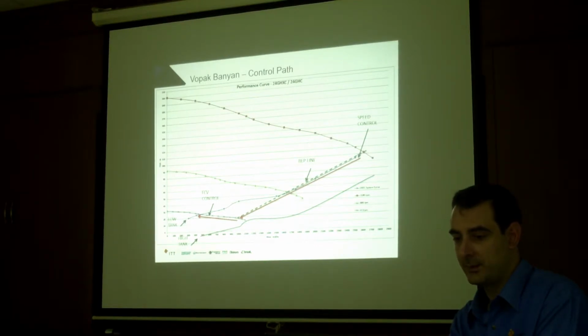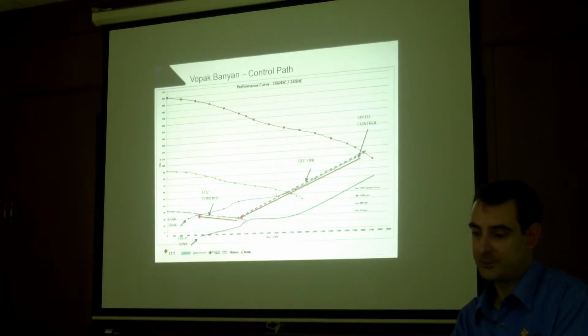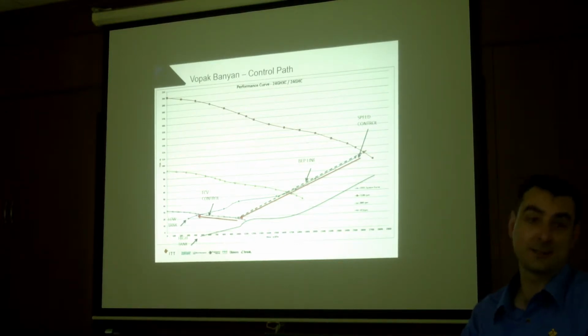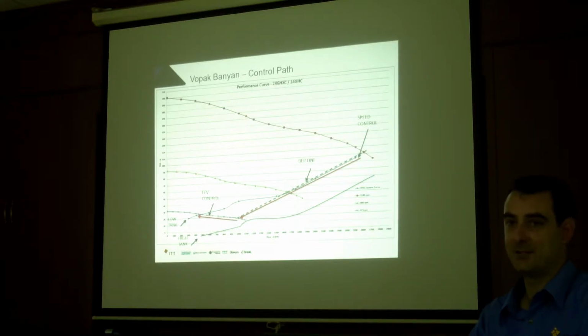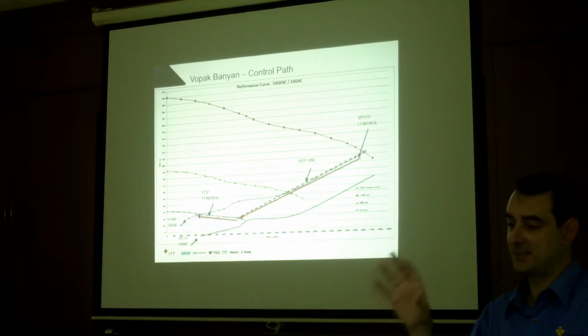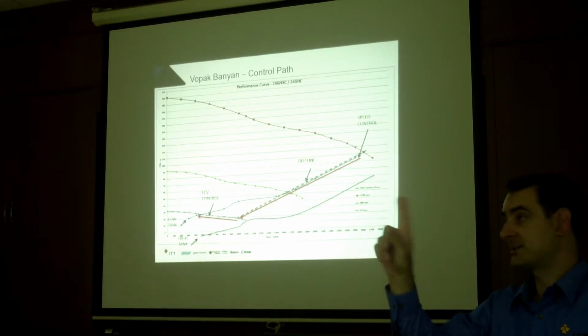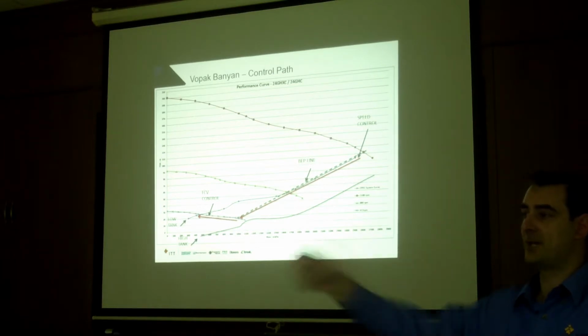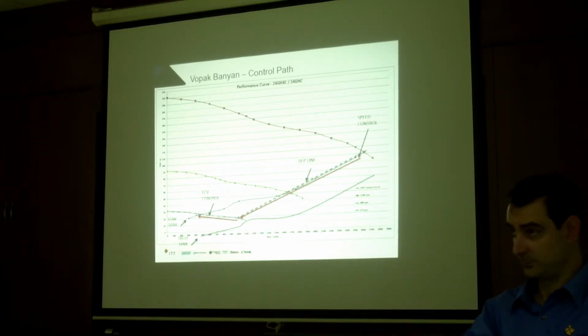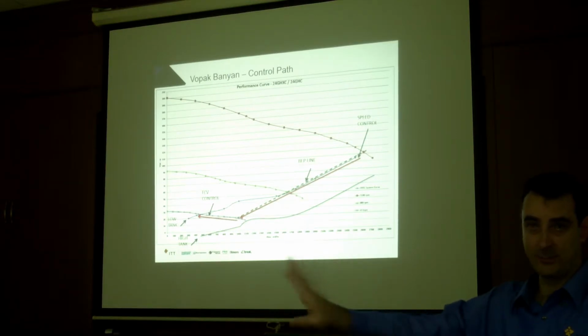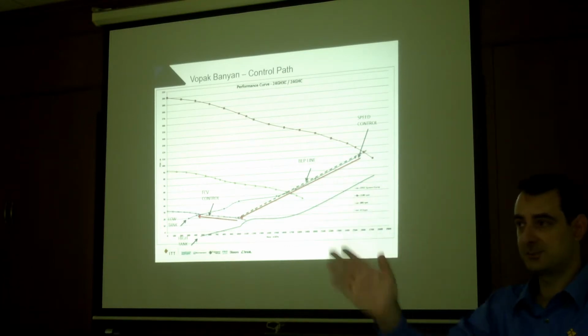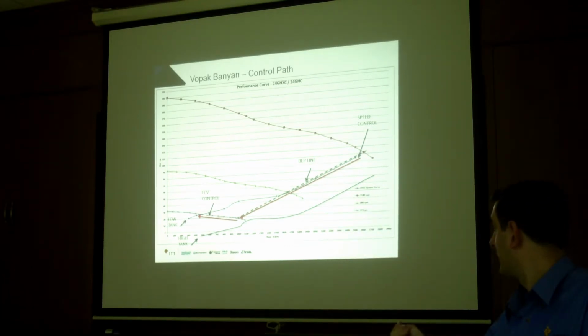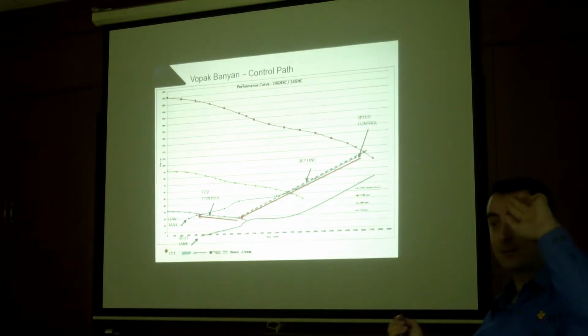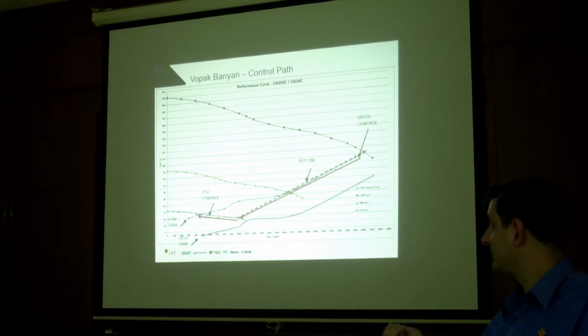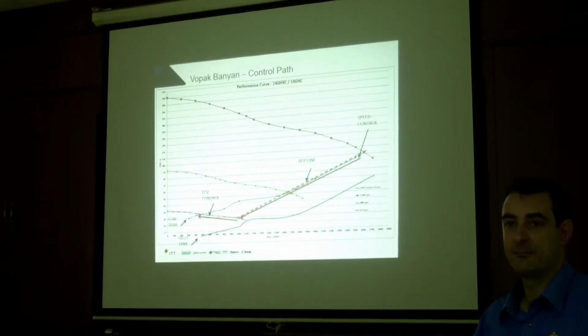Now, in terms of that, that's a medium voltage one. For the low voltage, I have a customer, again another Vopak customer, but a different site, where they had those Danfoss drives. We are using the percentage BEP value, sending it to the SCADA, to the DCS, the control room, and then they can see where they are, and if they're past 110%, they will send someone out to the field to shut the valve a bit. Once they shut the valve once, they will never need to worry about it again. The variable speed drive will do the rest, increase speed, decrease speed. But it's just to push them back onto the curve from the very beginning. Because they were off the end of the curve, when they have the lower tank levels, they just couldn't run the pump very well at all.